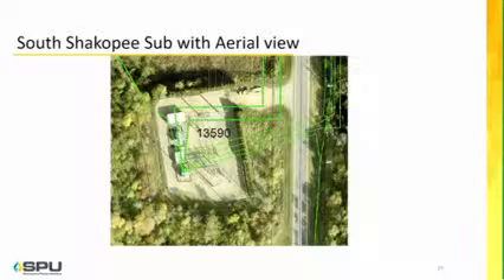So we had our first initial one, so that the tap comes in and goes back out, just like the one at Pike Lake. It's a little more convoluted, the way it's orientated. The substation's kind of rotated 90 degrees. And then we were able to add a second lineup in here. It's a very tight site. It's next to a wetland. And I'll cover some things, but you can see an outline here. This is a containment area, since the power transformers are all filled with mineral oil, no PCBs at all. Should they ever spring a leak, the oil will be contained inside this moat, if you will, until it can be pumped out. So it won't go beyond those limits and into the wetland or the environment.